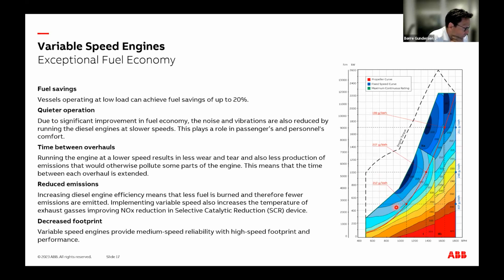So typically at this load, say 30% load, we would have 212 grams per kilowatt hour on variable speed. On fixed speed, I think it's 307, seems a bit much, but it's anyway much higher. It also depends on the machine. But this is important: it's a dynamic control that always controls online and optimizes the speed versus the load of the machine.